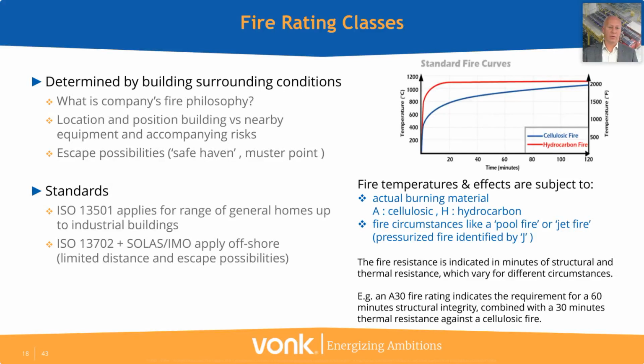If it is onshore, you have a certain ISO standard. If it is offshore, you have another standard whose requirements you have to meet. And also, depending on the sorts of fires, when the material in your building is mainly on a cellulosic basis or on a hydrocarbon basis, you have different fire ratings. These fire ratings are often indicated as a letter and a number. If it's an A30 fire rating, for example, it indicates a requirement of 30-minute thermal resistance and 60-minute structural integrity resistance against the cellulosic fire.